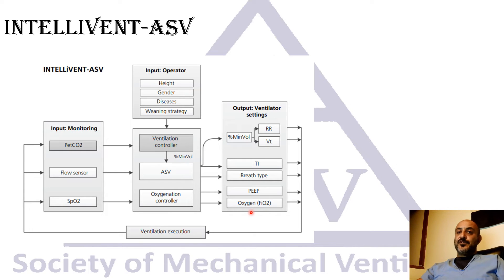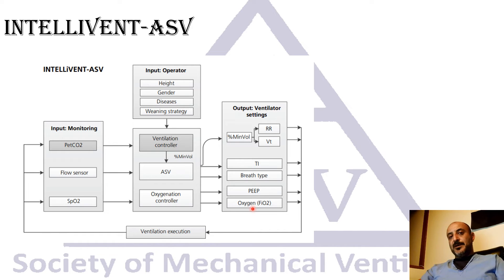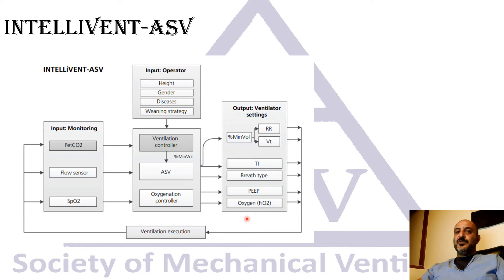A key new feature in IntelliVent ASV is the oxygen controller, which automatically adjusts PEEP and FiO2 based on SpO2. Currently this uses the ARDS Network PEEP/FiO2 table, but in the future it will likely adjust on a more physiologic basis.